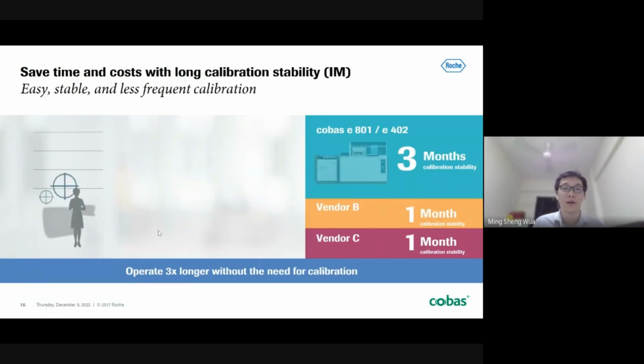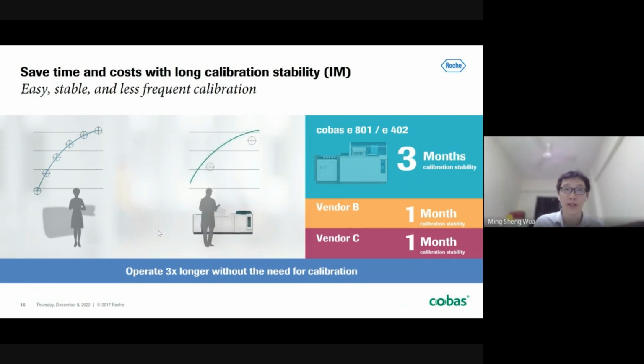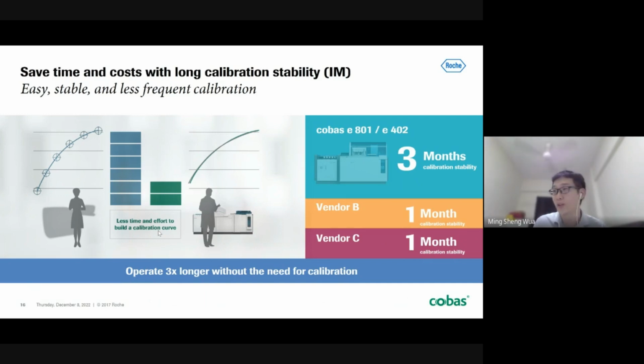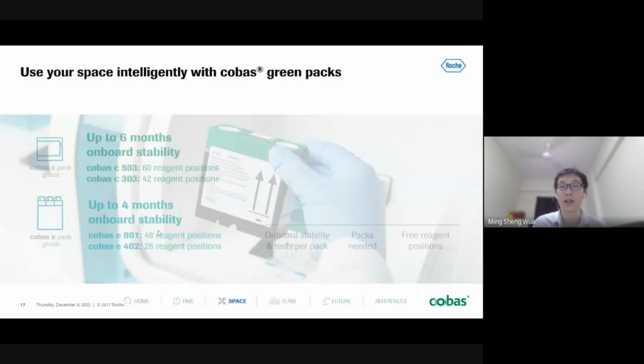When it comes to the immunoassays, we still need to do manual calibration, but the calibration stability has been increased from the conventional 1 month to 3 months. So this means that for immunoassays, your calibrations only need to be done about 4 times per year. This really minimizes the amount of manual effort that you need to do when it comes to calibration. So that is the second innovation.